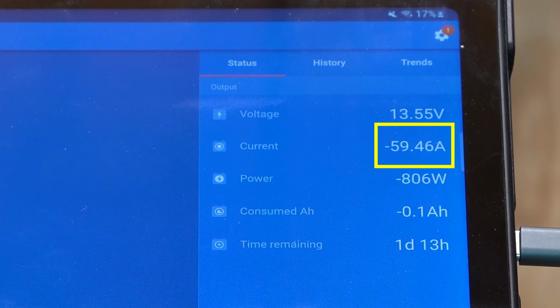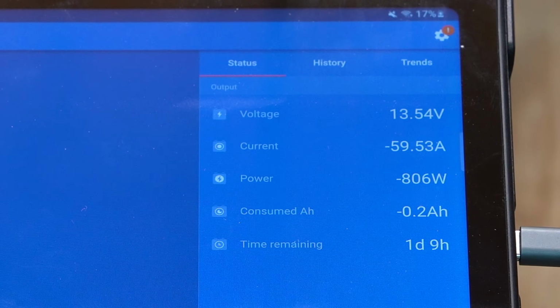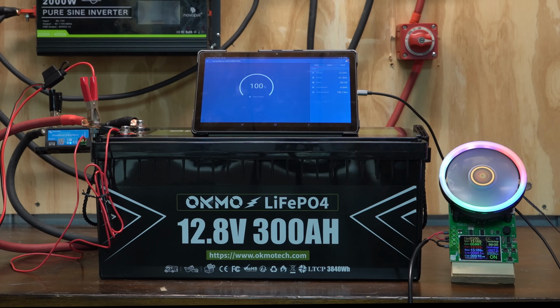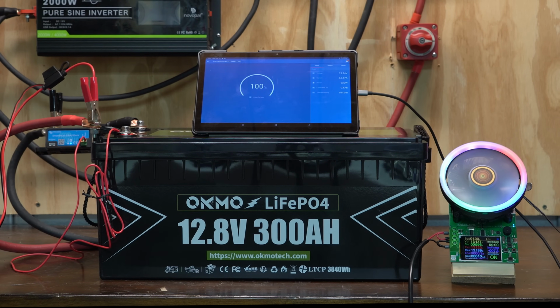Let me go ahead and start the battery tester and see if that puts us right at about 60 amps. I'm pulling 2 amps on the battery tester, knock that down to 1 amp, and that gets us very close to that 0.2C discharge rate. This should take something like 5 hours.